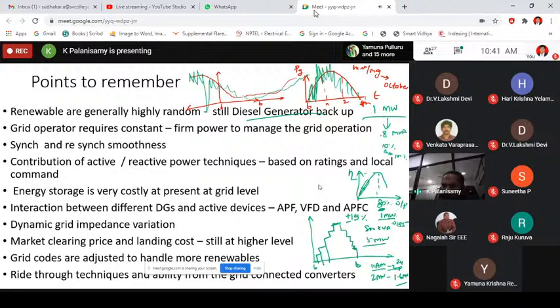What are the local variables? That is your voltage and frequency, right? When the frequency goes up, as I told you, I will reduce my active power injection. When the frequency comes down, I will increase the active power injection. Similarly for the voltage, if the voltage goes high, of course, as I told you, the voltage is not a global variable.